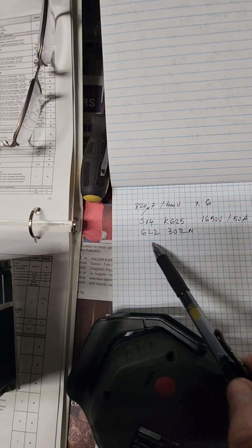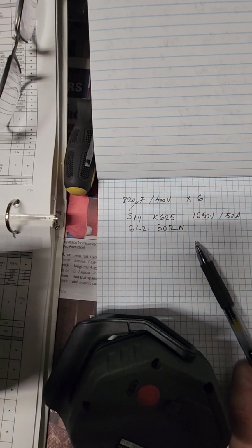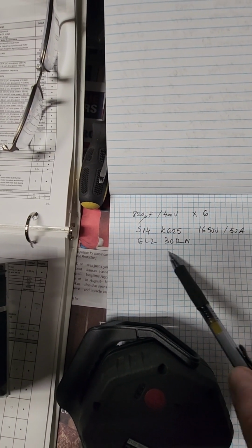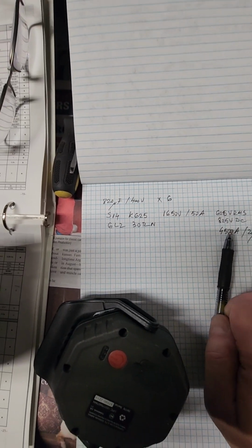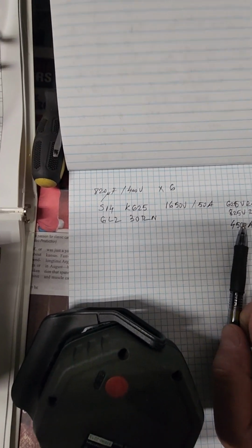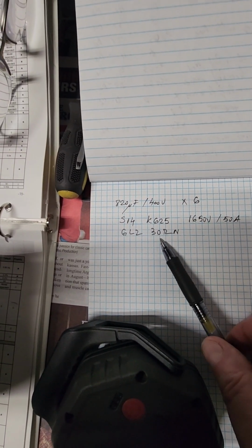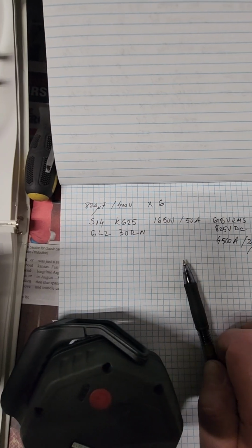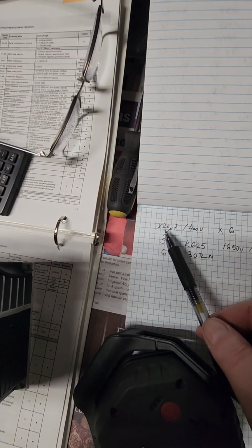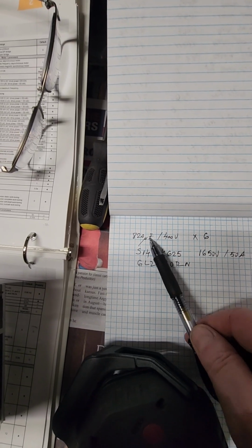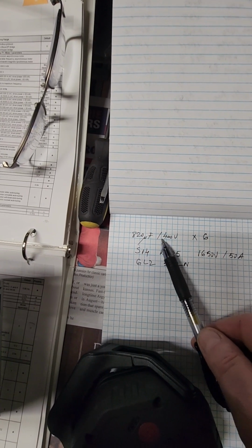I could not find online any data sheet for this. But supposedly this is the cold resistance, 30 ohms. So you put 380 volts through 30 ohms, you get 10 amps. The capacitor charges at 10 amps. This heats up, the resistance drops to 0 or very low, and then you get full current there. And as a DC bus, it's made of 6 capacitors, 820 microfarad at 400 volts. Maybe you can see there. But I'm not sure if that black thing there is a relay with a resistor or just protecting for current with these tiny NTC limiters.